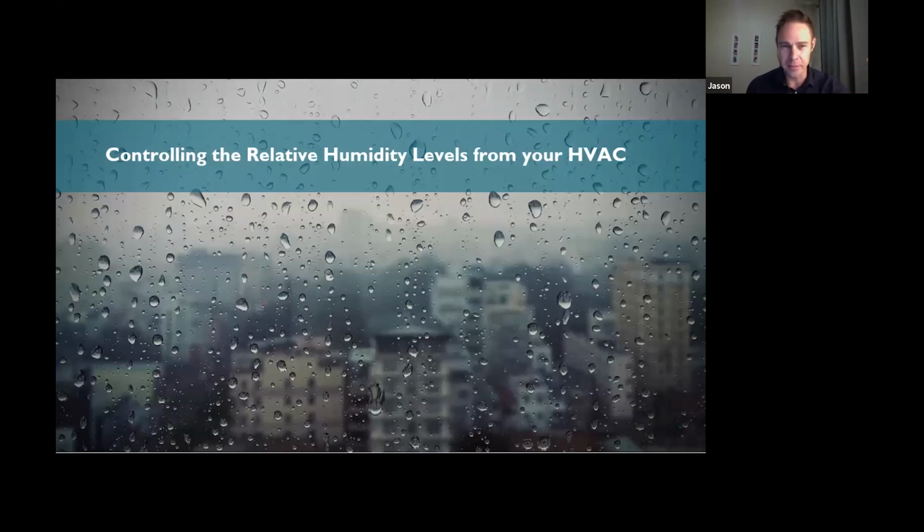the HVAC system. Since the HVAC system can make the indoor air drier than the outdoor air, it helps spread viruses more quickly. Note that the increase of humidity helps prevent the spread of viruses, but too much of it can also have negative effects. Therefore, striking that perfect balance is an absolute must. The US Environmental Protection Agency recommends between a 30 to 50% relative humidity level, while ASHRAE recommends 30 to 60%.